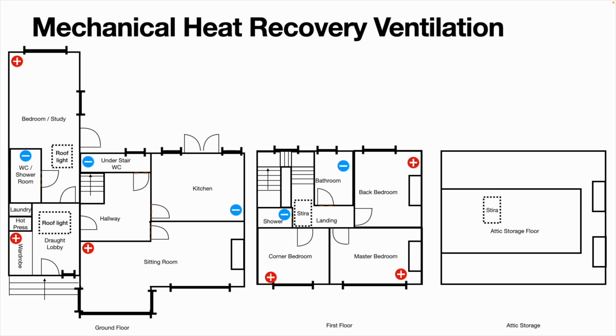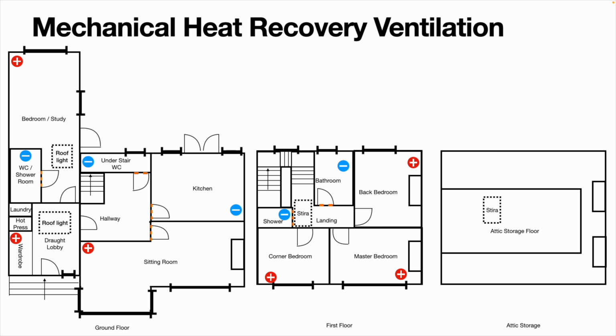The next thing to consider is that doors can be closed, so you'll see I've indicated where we want undercuts, where the bottom of the door is sliced off to let air travel underneath. In shower rooms, WCs and bathrooms, there's no problem having an undercut, letting air route in even when the door is closed. Otherwise you'd be forced to keep doors open to maintain airflow.